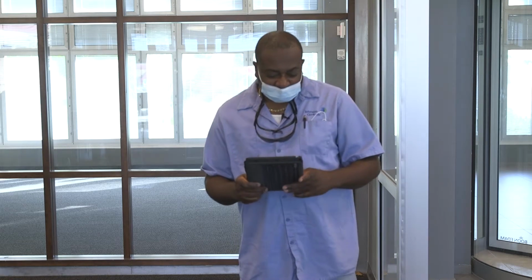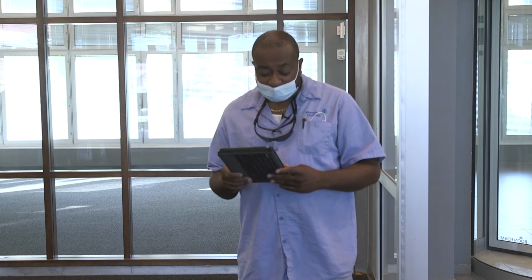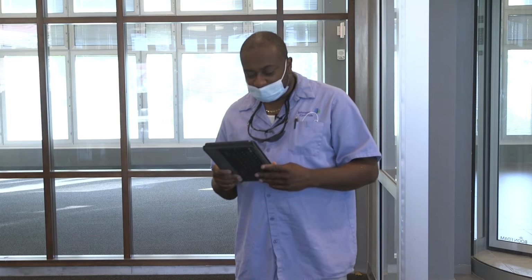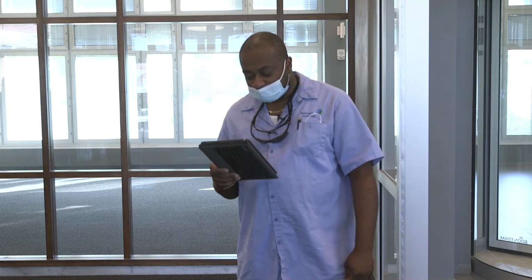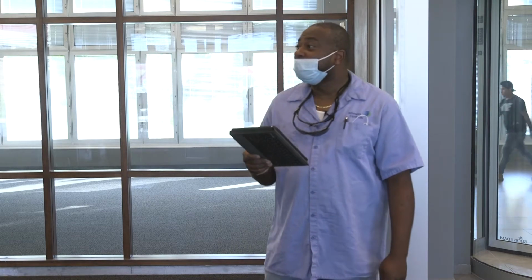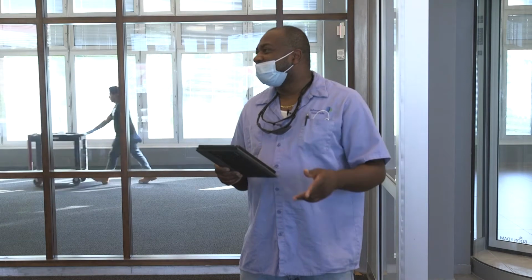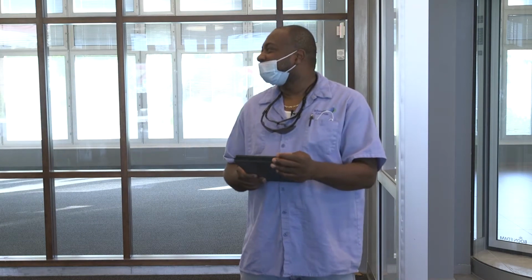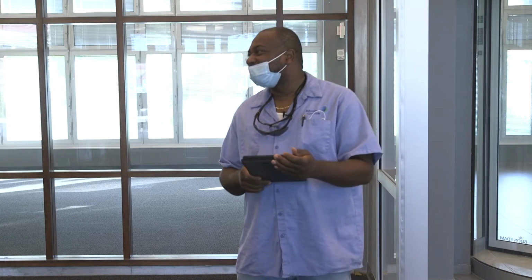This is the sequence of operation for the blower. With continuous blow, you set the room thermostat fan switch to the on position, and a 24-volt signal is provided to G1. By the way, after we finish here, we'll go by the actual unit, and if you have any questions, we can go over whatever we already went over here.